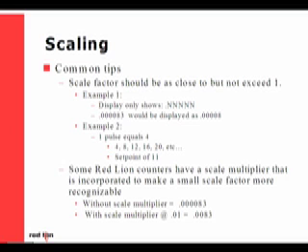Our progression will then be four, eight, twelve, sixteen, twenty, and so on. If we entered a set point of eleven, the counter will skip over that value going from eight to twelve and miss the set point.